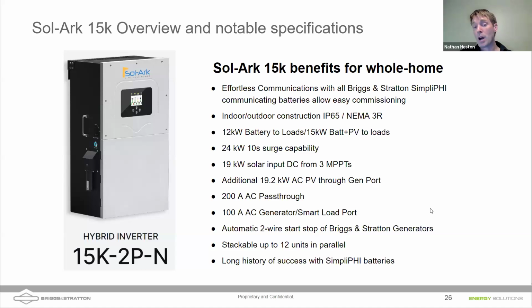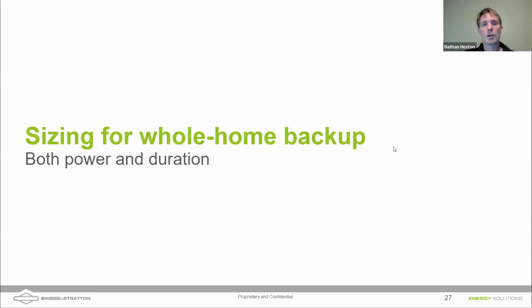It's stackable. You can monitor as well. You can monitor that generator input, you can monitor the grid input, and you can monitor your solar production. AC solar production is separated from DC, and the system's smart enough to recognize what you have. You can stack this inverter. So unlike the 8K, which was not stackable, the 12K, you were able to stack it. You can do 3-phase with 2 or more units. You can also do the same thing with the Sol-Ark 15K. So there's a long history of success with SimpliPhi batteries as well. We have been supplying our batteries with Sol-Ark inverters throughout the history of both SimpliPhi and Sol-Ark.